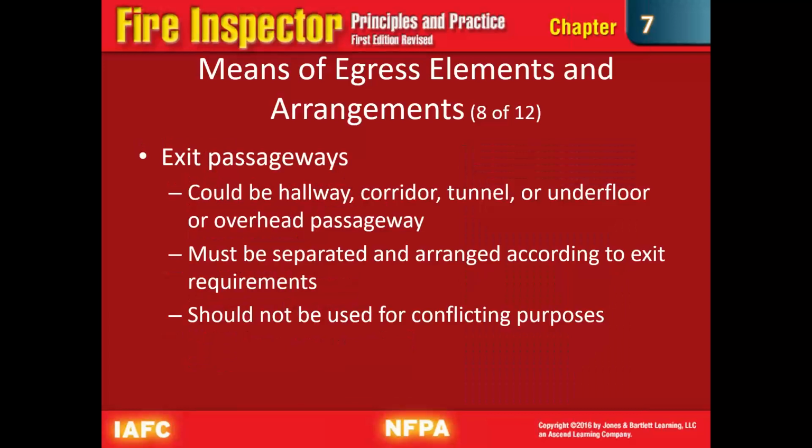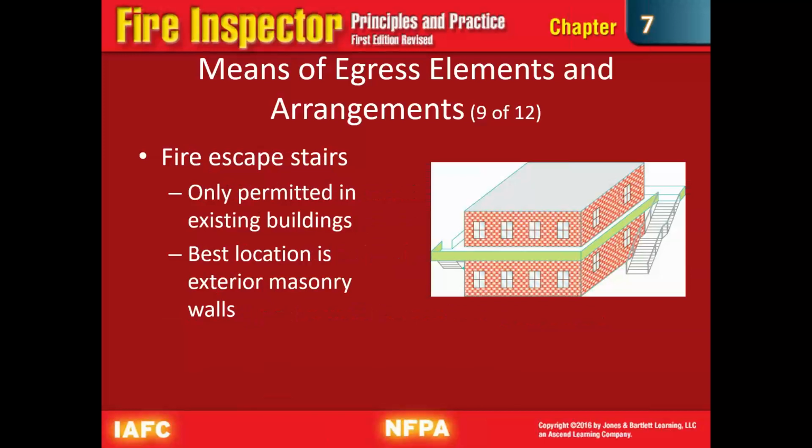All right, exit passageways could be in a hallway, corridor, tunnel, or underfloor or overhead passageways. They're separated and arranged according to the exit requirements and should not be used for conflicting purposes. All right, fire escape stairs.